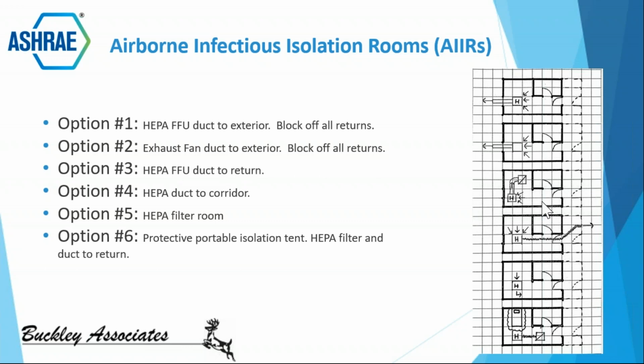Option 4 here shows another HEPA filtered air being pulled out via this fan filter unit and being ducted into the corridor facility. Now, again, we'd rather get the stuff outside the building, but if the only way that we can keep this patient safe and build this isolation room is by HEPA filtering this air and then pulling it out, this is another viable solution that ASHRAE is presenting. Now, option 5 here doesn't allow for any isolation and pretty much should be the last case scenario, where some filtration is going to be utilized just to help prevent the buildup of the virus in the air.